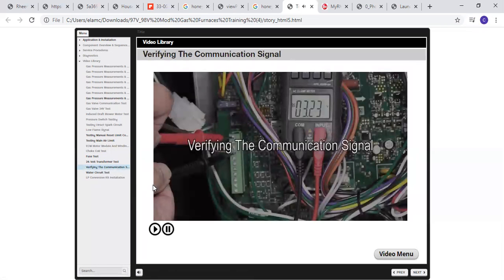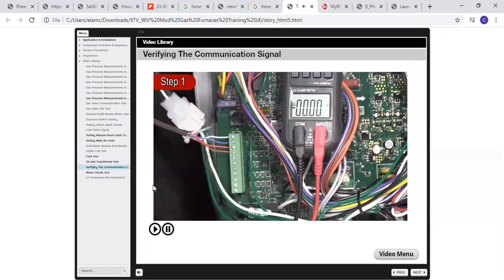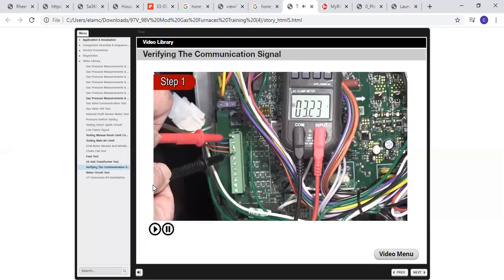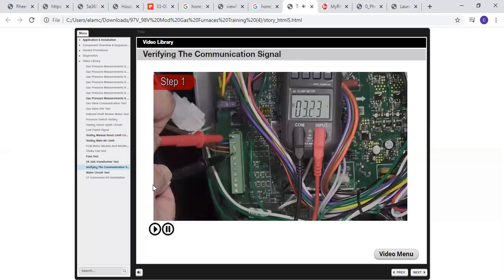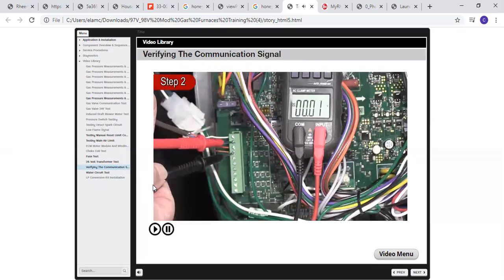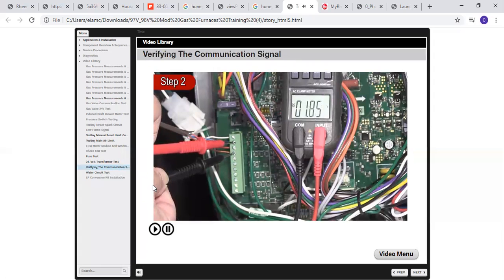Verifying the communication signal. Step 1. With the system powered up but with thermostat off, check for a fluctuating DC voltage between E1 wire terminal 1 and C of the furnace. The voltage will vary between 2.5 to 3.5 volts DC. Step 2. Check for a fluctuating DC voltage between terminals 2 and C of the furnace. The voltage will vary between 0.3 to 1.8 volts DC.